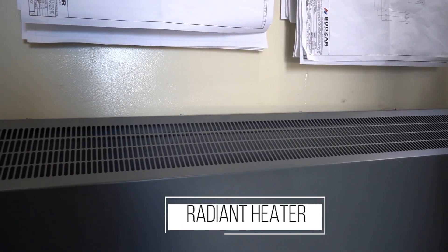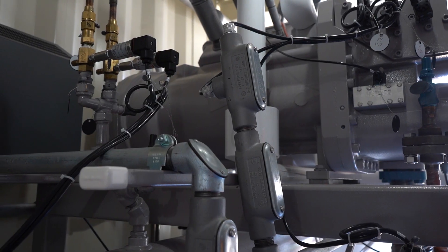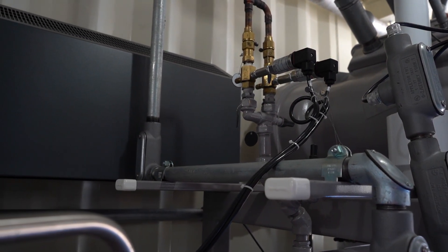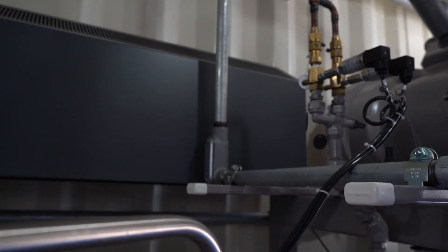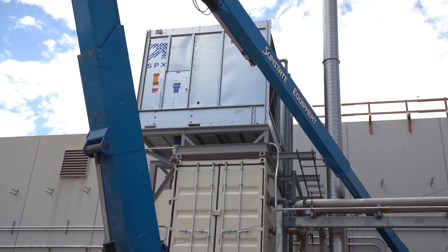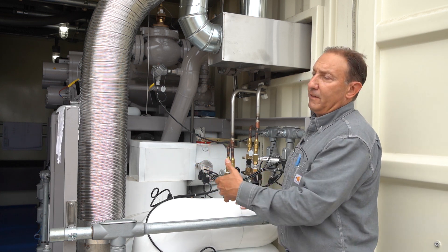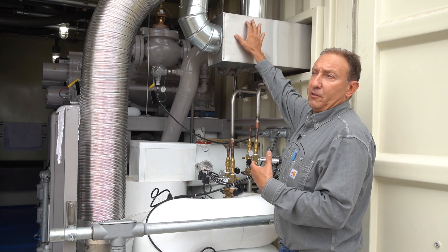The chillers were manufactured inside a container. They have a ventilation system for safety purposes and heat control, trying to keep the temperature below or around 90 degrees Fahrenheit. It's all explosion proof, class one, div two rating, with purge panel systems. Everything is contained in the containers and we have the evacuation system. Due to the flammability of the refrigerant and the electrical involved in the class one, div two area, we have an elaborate exhaust or ventilation system.